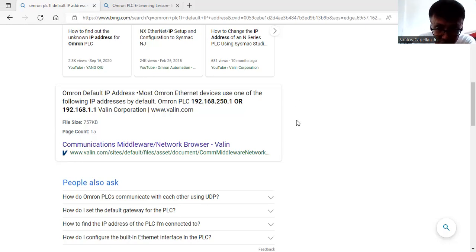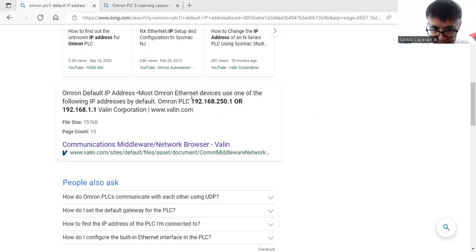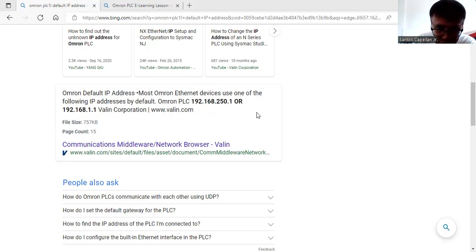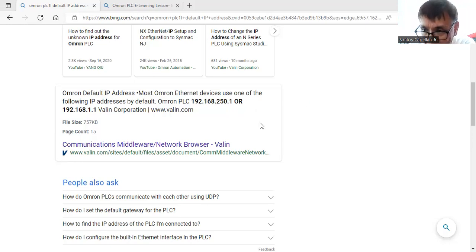I went to the Omron site and found out that the default IP address is 192.168.250.1. So that is the default IP address of my PLC. This is a Class C address, meaning 192.168.250 is the network ID.